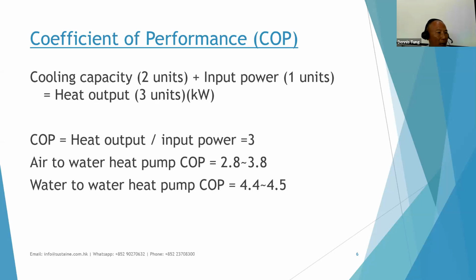Currently in the market, there are many kinds of heat pumps. The commonly used one is the air to water heat pump, which has a COP of 2.8 to 3.8. And the water to water heat pump has a much higher COP, which is 4.4 to 4.5. So we can see that with the use of a heat pump, we can generate heat energy within the building with very effective COP or efficiency.